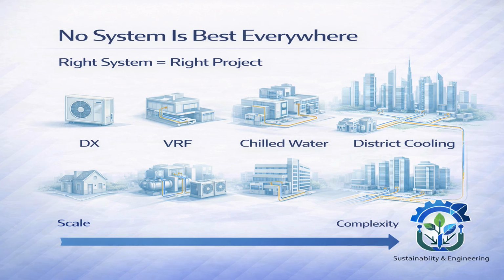Next comes VRF. VRF sits in the medium scale range. It is perfect when zoning is required, loads vary throughout the day, and partial load efficiency is important. VRF bridges the gap between DX and chill water. But once the building becomes very large or runs 24/7 or has heavy fresh air requirements, VRF starts reaching its limits.